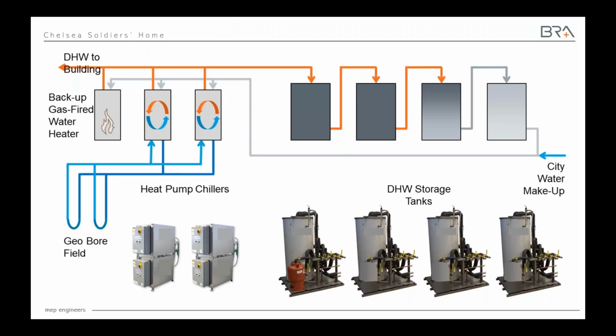And then for domestic hot water, again, you know, heat pumps are not cheap. So when you've got a system like domestic hot water that can have very high peak demands, if a large percent of people take showers at the same time, you're gonna have a lot of demand to heat that water up very quickly.